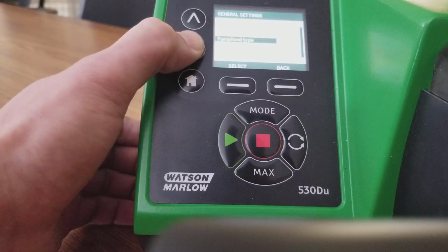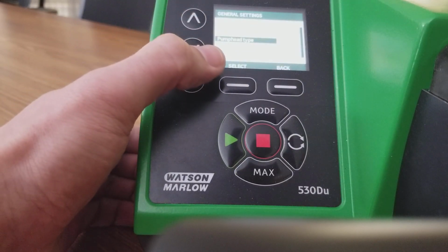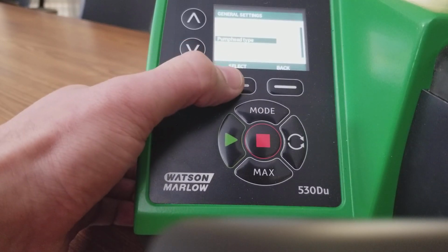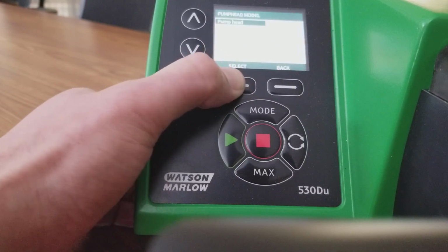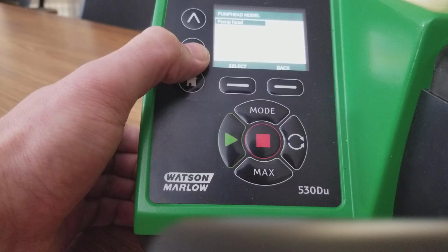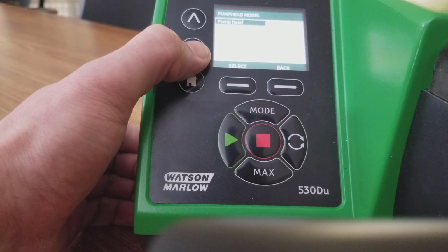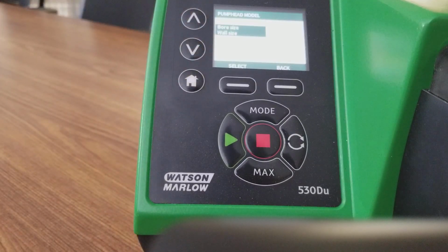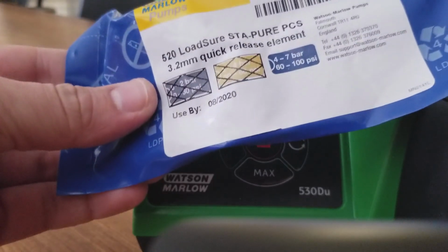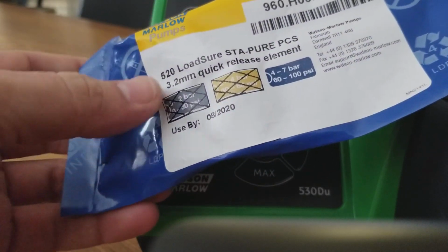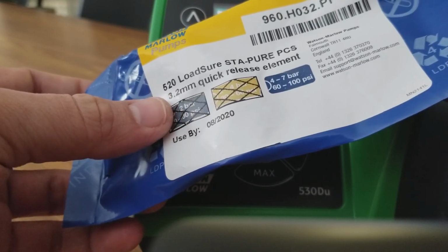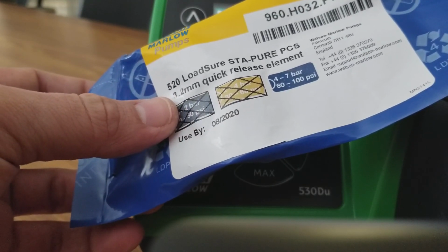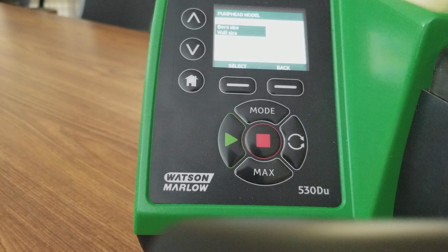The next thing we want to do is make sure that our pump head matches what we're actually going to be using for the tube, which makes calibration a lot easier. So on here, we'll continue to use the 520 R2 because that's what would be found inside the case. Our bore size is the most important part, and if you take a brand new bag, you'll see that right here where it tells us our 3.2 or so on is where our bore size will be found.